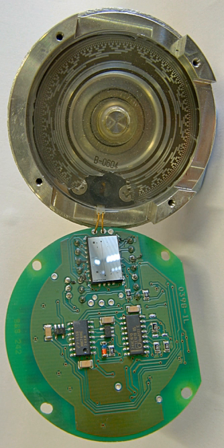The absolute analog type produces a unique dual analog code that can be translated into an absolute angle of the shaft by using a special algorithm. Due to the nature of recording magnetic effects, these encoders may be optimal to use in conditions where other types of encoders may fail due to dust or debris accumulation. Magnetic encoders are also relatively insensitive to vibrations, minor misalignment, or shocks.